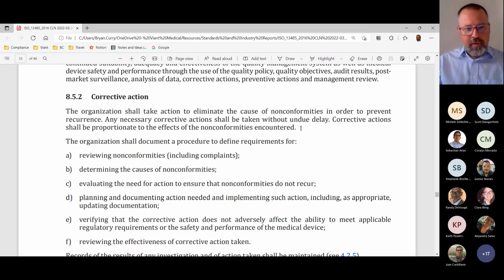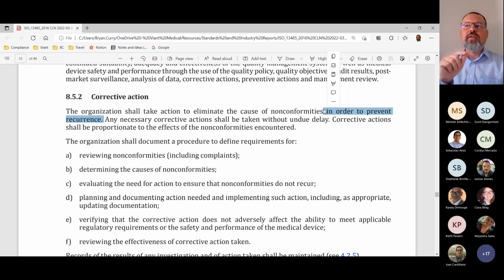So your procedures for improvement, or your procedures for corrective and preventive action, shall be structured in a way that you are taking action to eliminate the cause of nonconformities. Now, those nonconformities could be nonconformities in product. It could be nonconformities in your actual quality management system. And the intention is that you prevent recurrence. Now, this is an area that is also a little bit open to interpretation, this concept of prevent recurrence. And I would say that frequently in the execution of your corrective and preventive action program, there are going to be times when you identify a failure mode of some kind, and this is more along the lines of product nonconformity than it is system nonconformity.